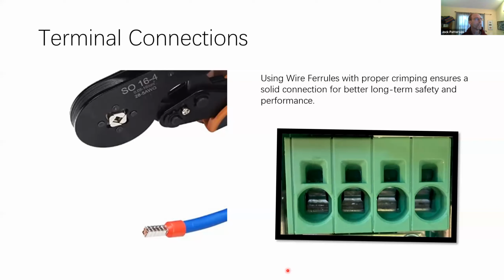What's recommended is you can get this crimping tool. There's a ton of them on the web that create this square crimp. We provide these what are called wire ferrules in the box. You don't have to use them, but we recommend you use them because if you ever look inside at the jaws of these terminals, they're square shaped. They're not round. Yeah, they're round going in at the insulation here, the dielectric. But when you want to insert the wire and you want to control those strands from splaying out, it's great to use this crimper. It's inexpensive, 25 bucks. We provide all the actual wire ferrules. You crimp them and they push in nice and easily, create good connection, reduce the chance of any connection resistance over time. So we highly recommend you use those, but you don't have to.